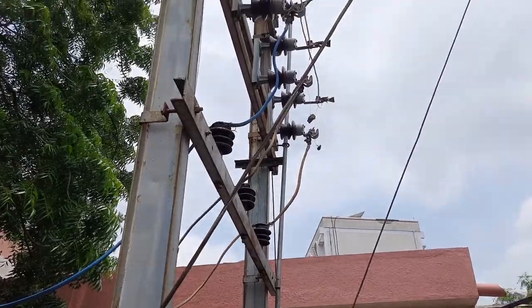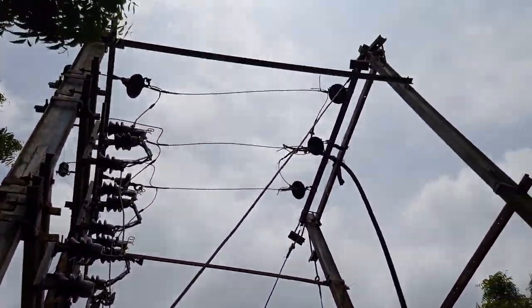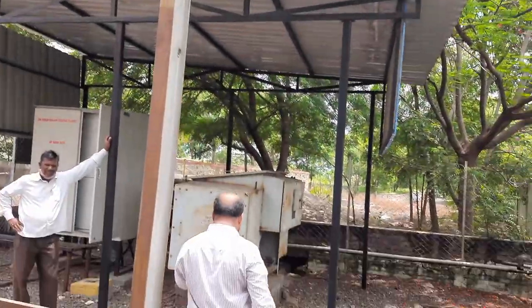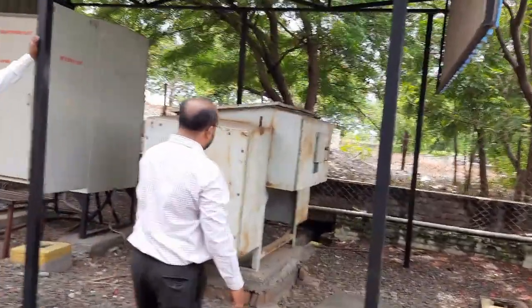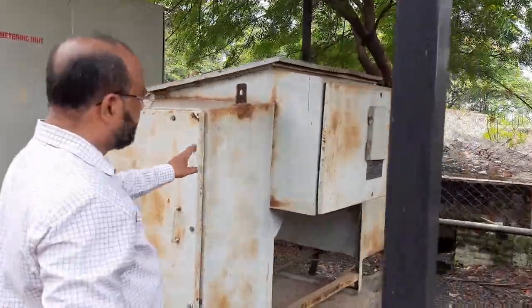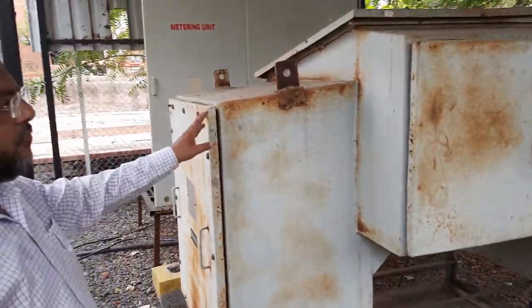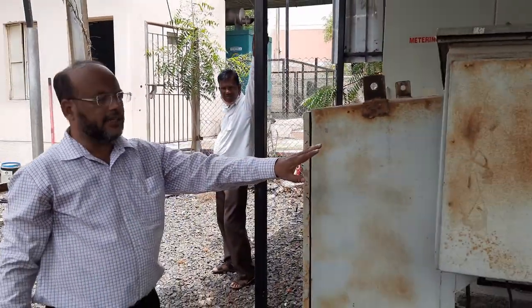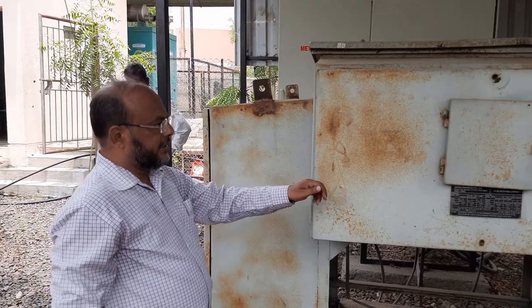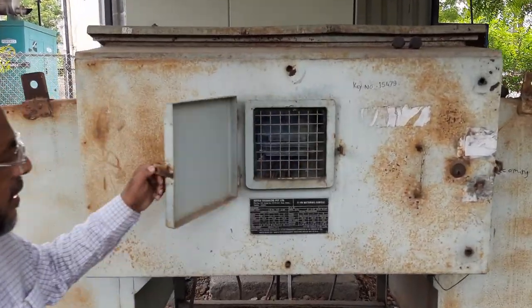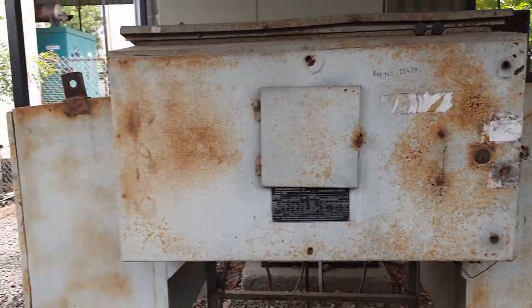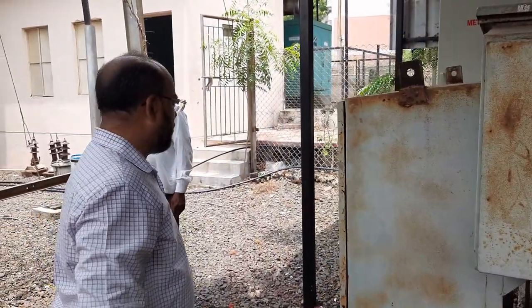This is the 11 kV metering unit. It comprises an HT voltage transformer, that is a PT, and CTs. With the help of the PT and CT, a bidirectional energy meter is under the custody of MSEDCL. This bidirectional energy meter measures incoming and outgoing energy, as we have a solar power plant.